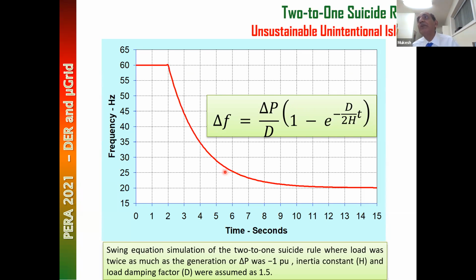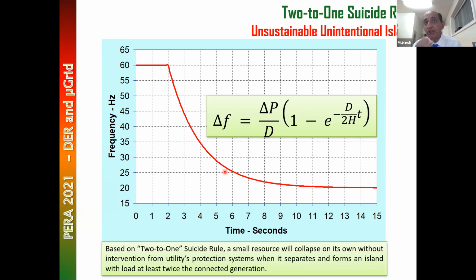We have published it, and it's now an industry accepted rule. The 2:1 rule is not about load damping. The 2:1 rule is a margin. What if your load today is twice, and tomorrow is 1.8? If you go by 1.1, let's say your generation is 1 and load is 1.1, and tomorrow, for some reason at some time of day, your load is lower than 1.1, then you can form a sustainable island. The point we're trying to make is an unsustainable island. The 2:1 rule is to guarantee that your island will not sustain.